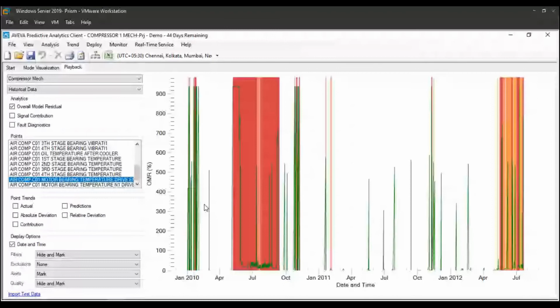Okay, so if we don't have a historical data set, I'm alluding to the question from Mr. Dhiraj sir. If you don't have a historical data set, there is no way for the software to know what the ideal or normal condition for that particular equipment is. So what we do not do here is give it a particular OEM recommended value for an equipment. For example, we will not simply say that the OEM recommended temperature is 60 degrees. What we'll tell the software is that this is how this particular variable has behaved in the past, and we consider this past history of the equipment to be normal for us. That is what we teach the software.